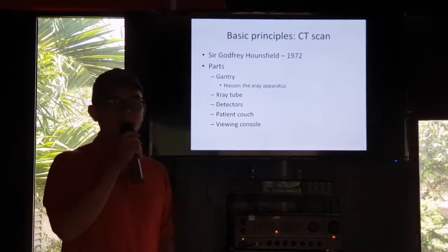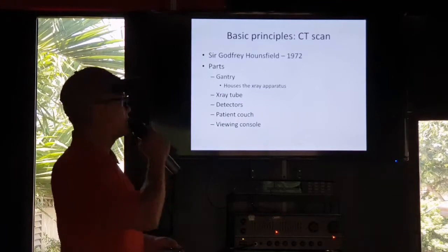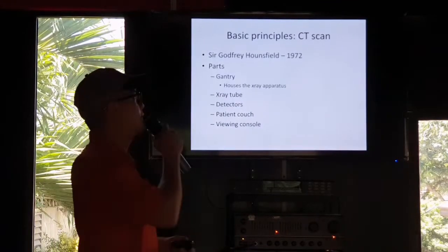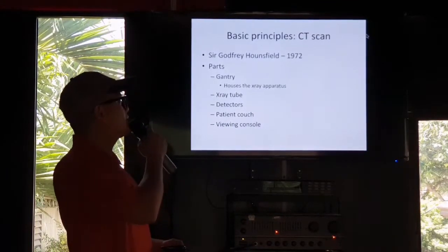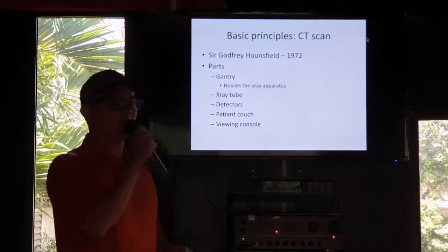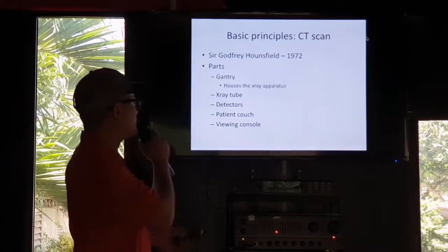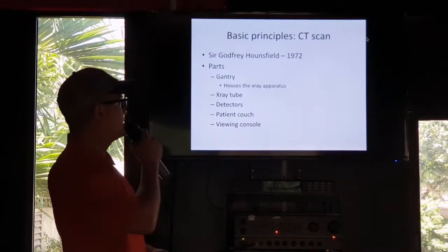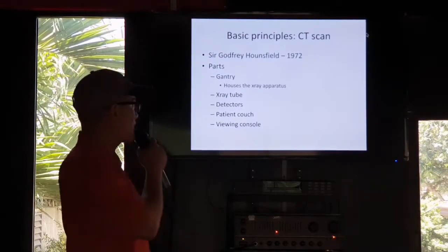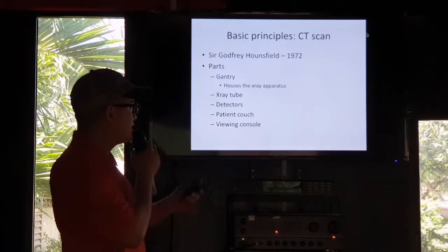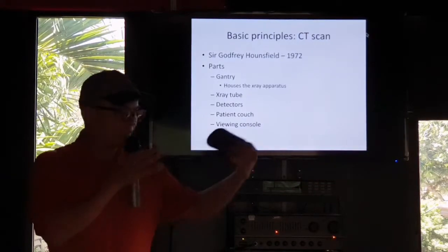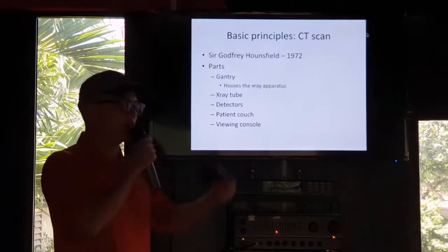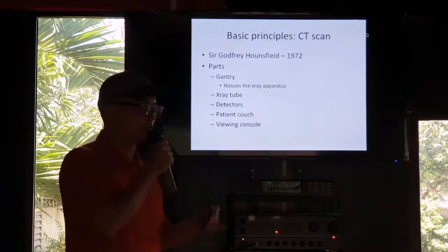Okay, CT scan or computed tomography scan. Computed tomography. It was discovered by Sir Godfrey Hounsfield in 1972. And these are the basic parts of the CT scan. So you have the gantry, which houses the X-ray apparatus. The X-ray tube, you have the detectors for the X-ray.